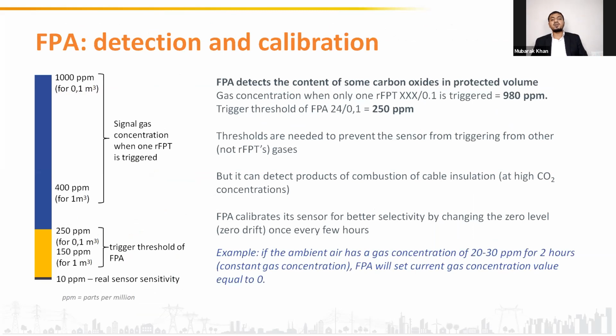FPA detects the content of the gas in a protected volume. The gas concentration when only one rFPT is triggered is around 980 ppm. The trigger threshold of FPA is 250 ppm. That means that even if more than 50% or 70% of the gas has escaped from the panel because of holes, openings, or the door being open, FPA will still be able to detect the gas. So there is a very low probability that because of openings in the panel, the gas may be lost and cause misoperation. It is not possible because we are using 300% redundancy of the gas.